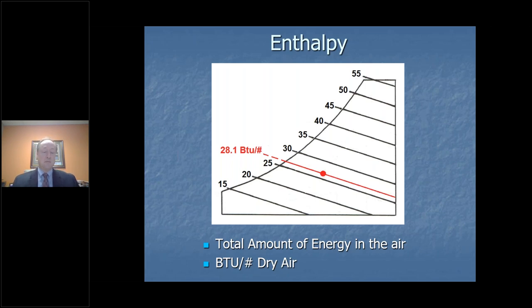It could be some sensible heat coming off of your body, but all of this heat that comes into your space increases the temperature from the left to the right, and that adds energy. So you can imagine right here, if you were at this particular level, well, let's say you're on this level here, you might be at 25 BTUs per pound. And as you increase the dry bulb temperature, you're moving from left to right, and now you'll see that you go up to this chart and you'll see you're at 28.1.